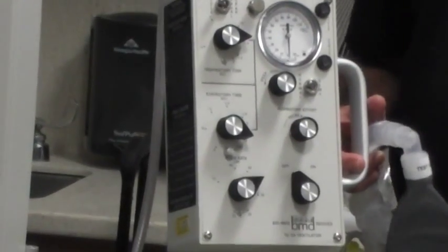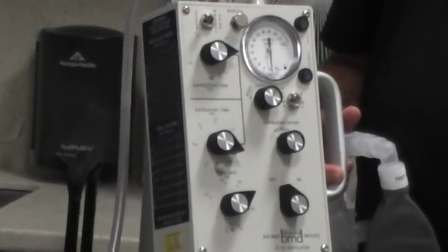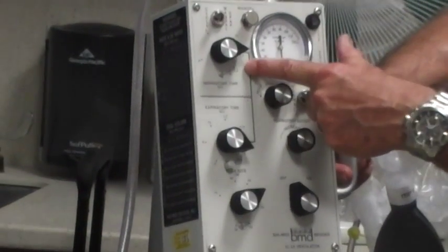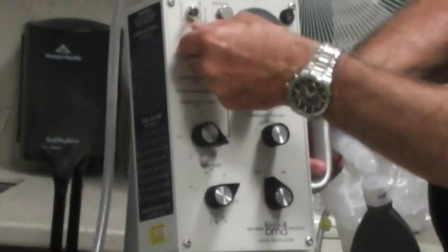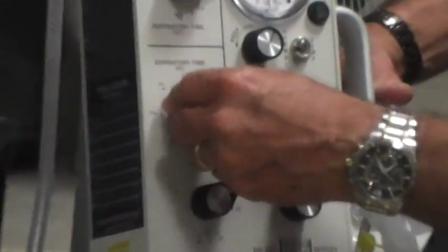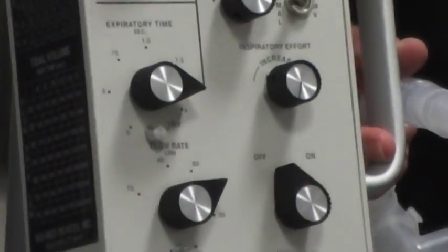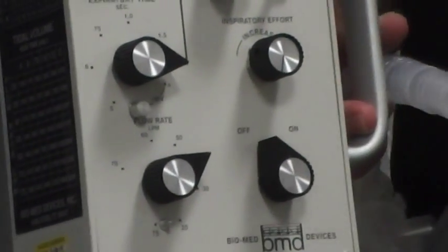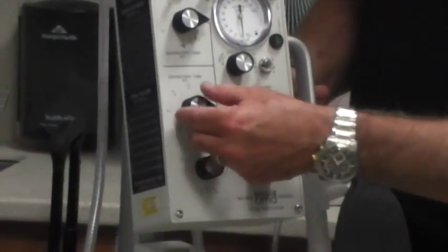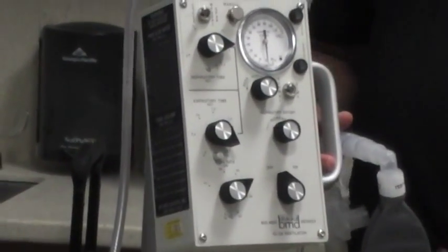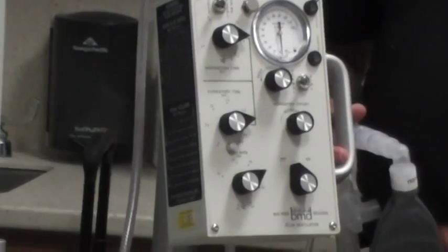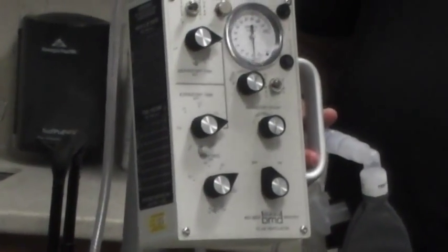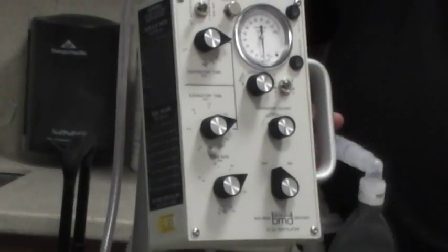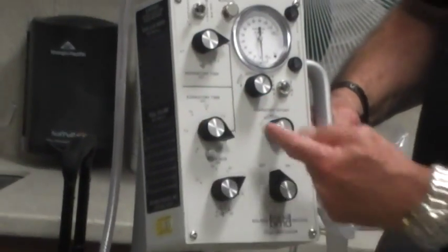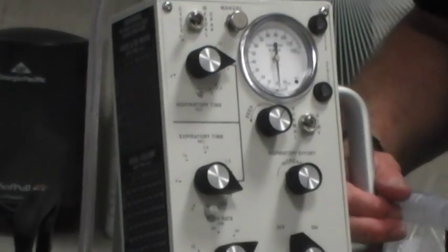Now what if I wanted a rate of 16? Well, it's halfway between 12 and 20. It would be 3. I don't have a 3, I have a 2 and a 4, but there's a 3. Exactly. So literally, you can set any rate you want. If you need a slower rate, you have a longer expiratory time. If you want a quicker rate, you do shorter. And you can always look at the watch and tweak it to exactly what you want. So that's how you'd set the rate. I'll leave it at 4, which is a rate of 12.